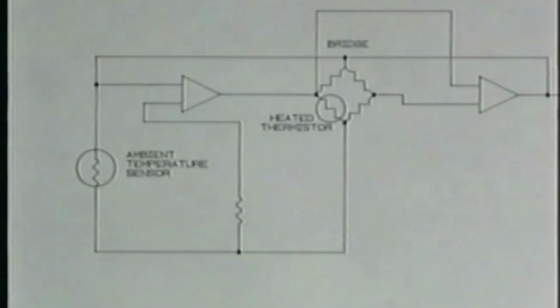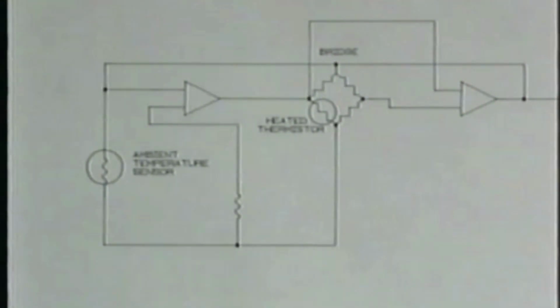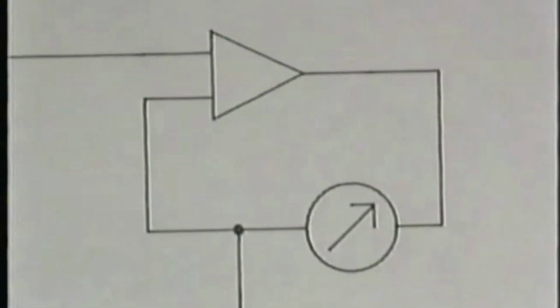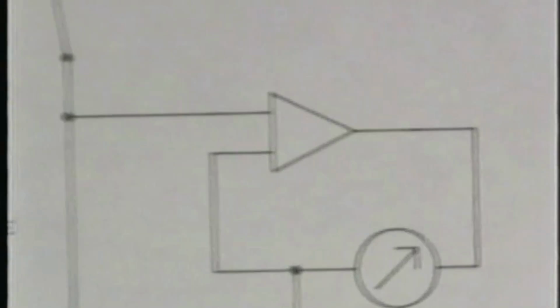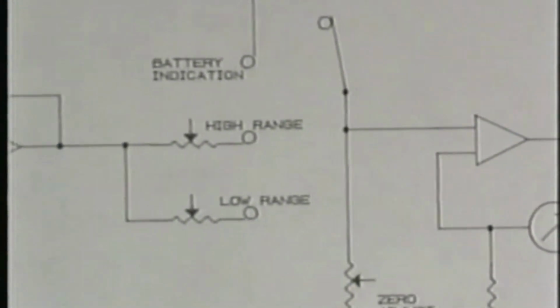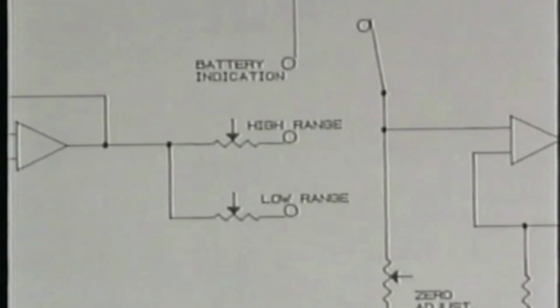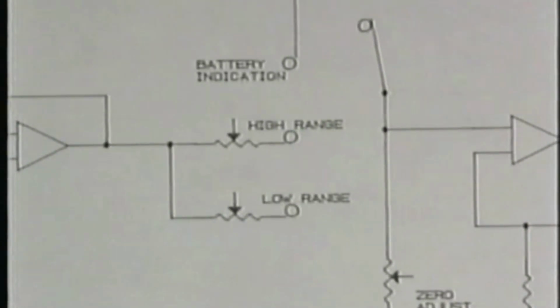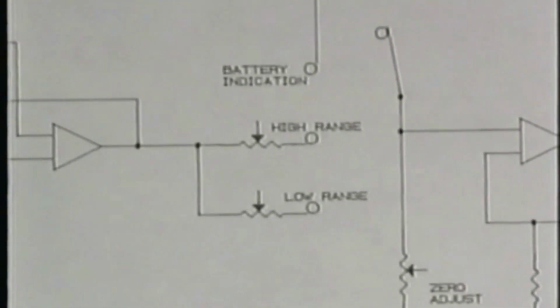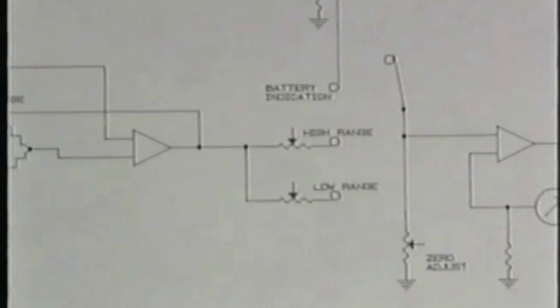The thermistors form part of a bridge circuit, which is used in conjunction with an operational amplifier to create a current proportional to the voltage change. This current drives the meter. The range switch changes the amplification factor, allowing air velocity to be displayed on either a low or high reading scale. The switch also has a battery position labeled BAT, where a portion of the battery voltage is substituted for the bridge output, giving an indication of the voltage being provided by the battery.